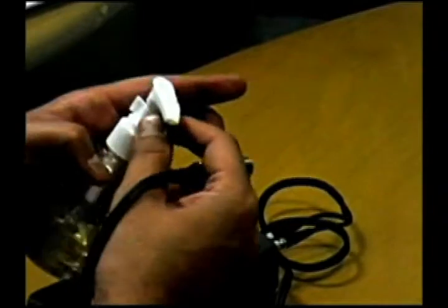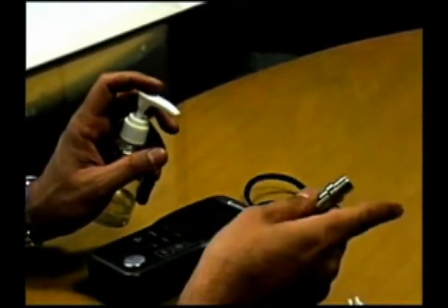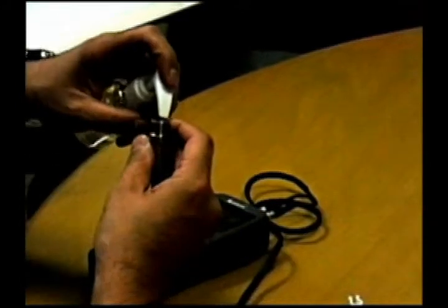We then use a couplant. A couplant is utilized to create conductivity between the transducer and the material that we are able to test. So we put some couplant over here on the top of the transducer.